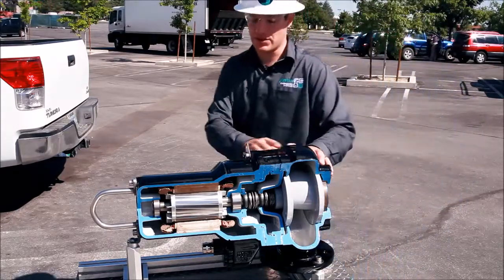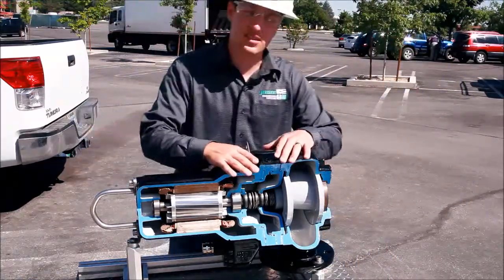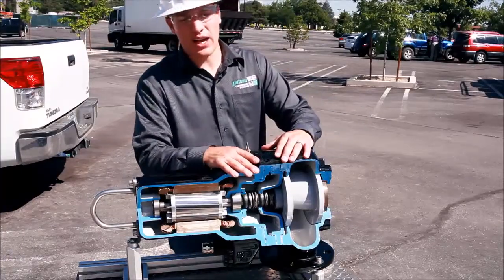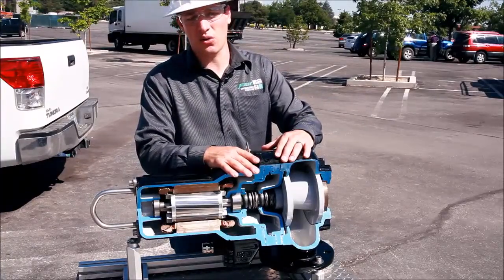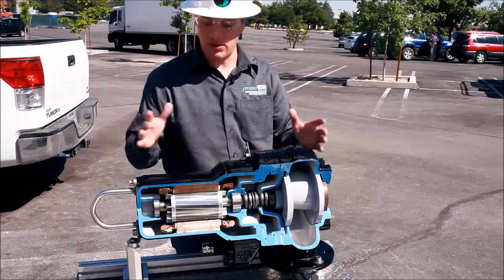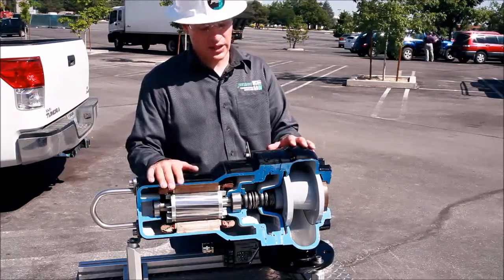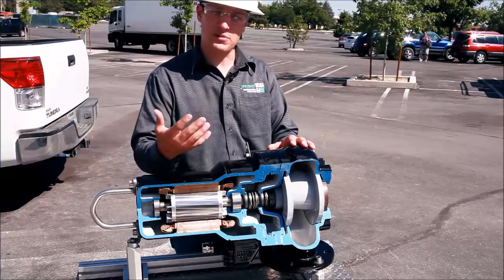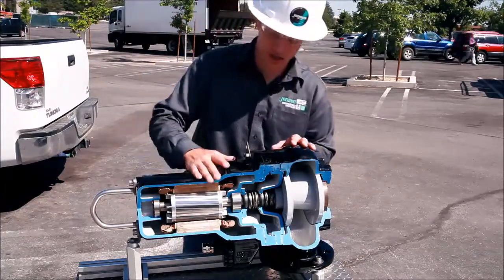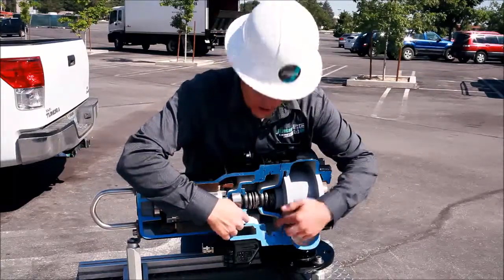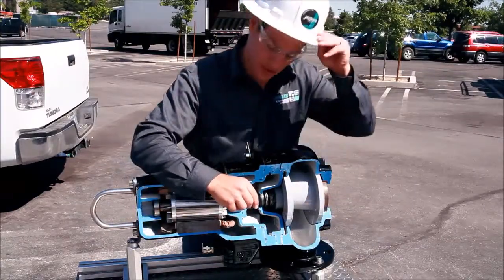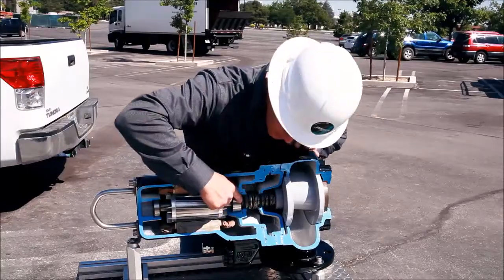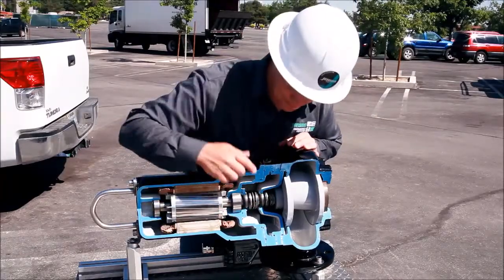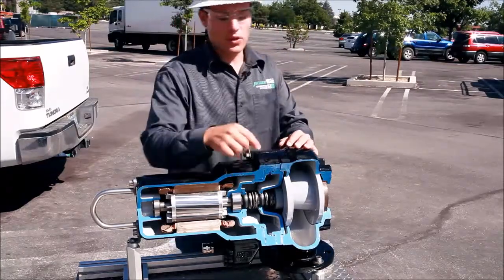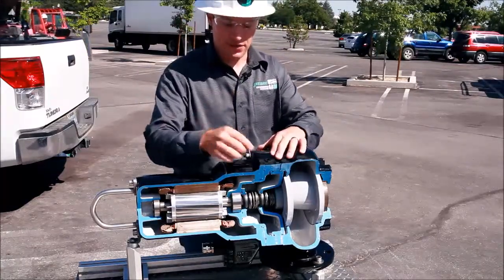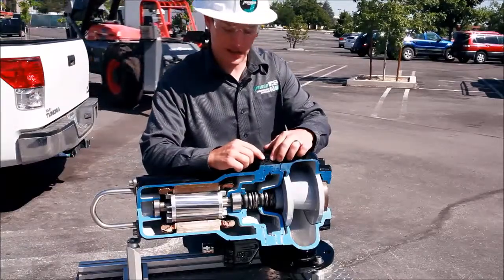As we move up the pump assembly, we then get to the oil chamber. The oil chamber houses a white mineral oil that can be found at any local pharmacy. There's nothing special about white mineral oil in the operation of the pump. What it's doing is telling the control panel if there's been a seal fail in the pump. The way it achieves that is, in the oil chamber, we have two mechanical seals, a lower seal and an upper seal right here. If water was to... and then on the top of this, I don't know if you can see it from the video angle, but there's a plug right here with a hex head in it.